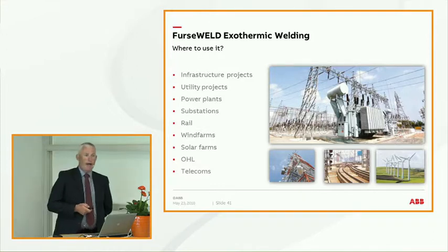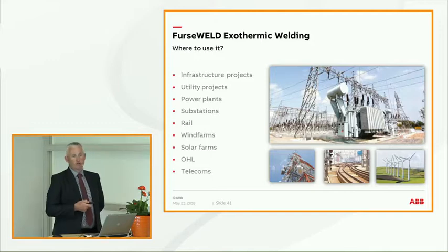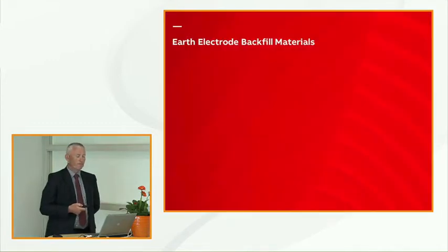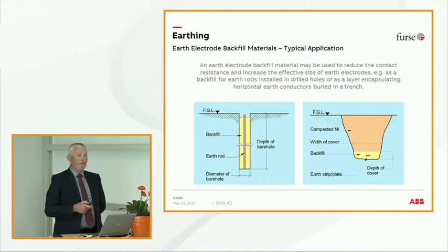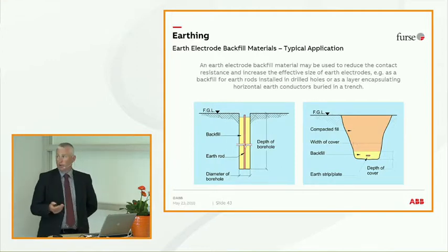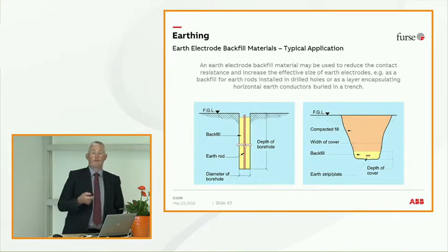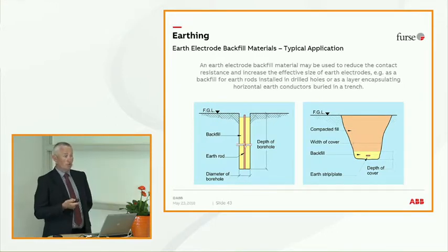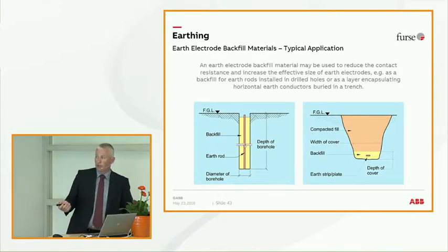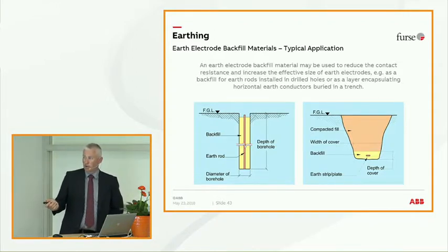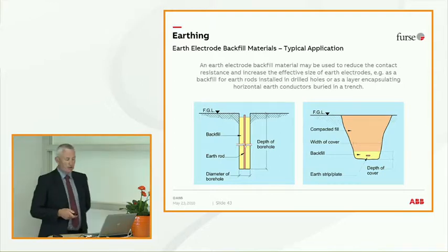When looking at your earthing conditions, I've mentioned the soil resistivity can be an issue. We get involved with backfill materials. You might have come across carbon components like marconite. So a typical application, you could have a borehole. If you've got sand or you've got rock and you're going to struggle to get the right earth reading, we can put a borehole in place. We can dig a trench and we can put this earth conditioning agent in place.